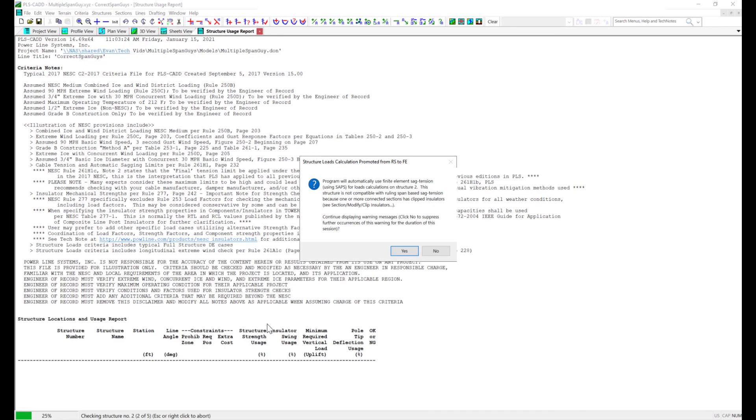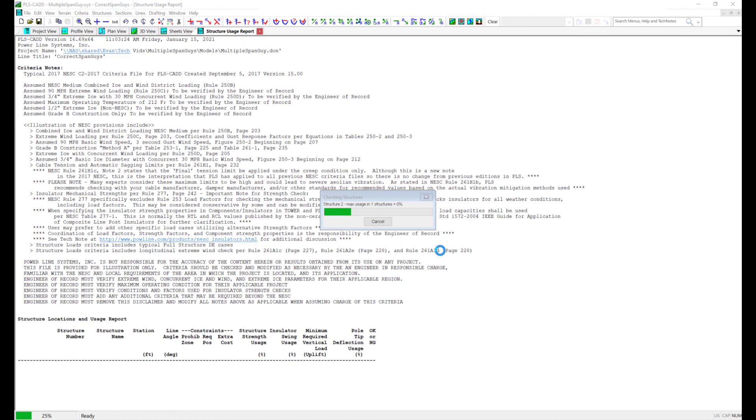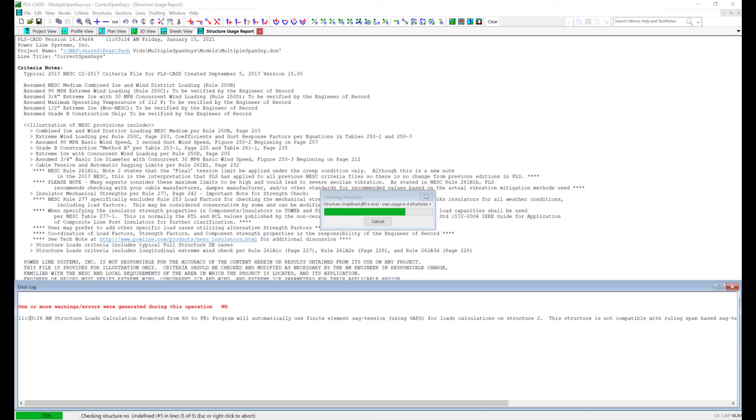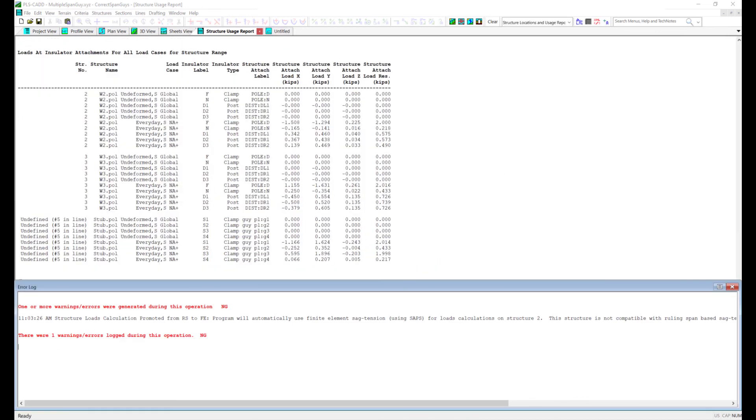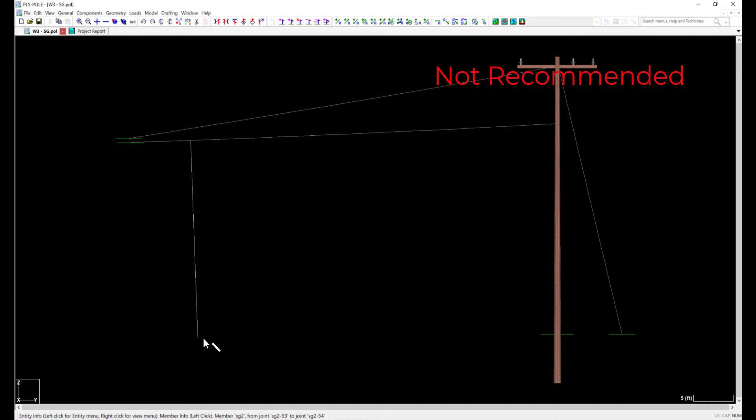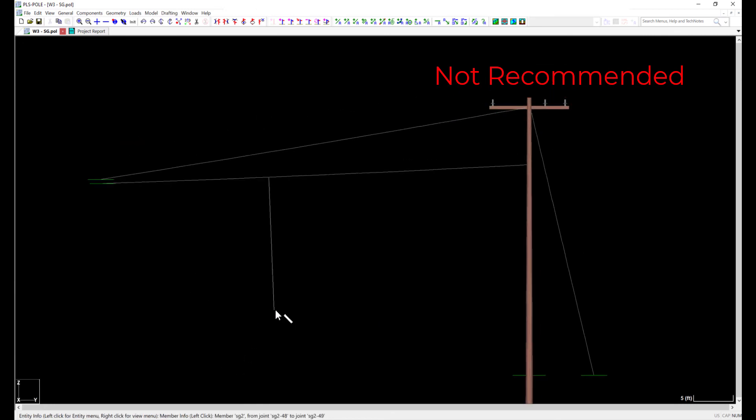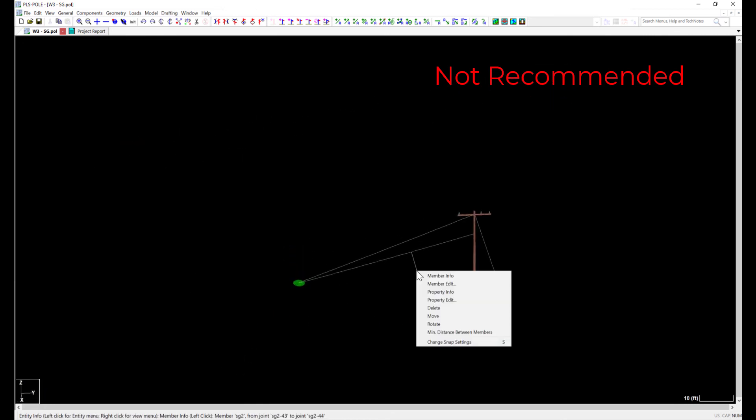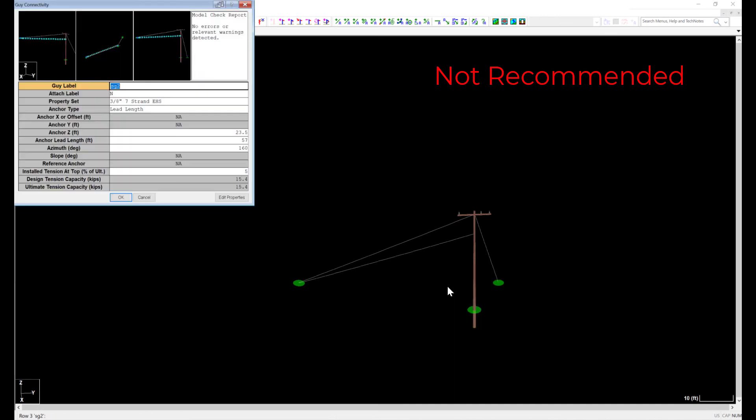I want to point out something while I run this analysis. We see sometimes that users will create separate models, but instead of connecting the models with wire in PLS-CADD as I have done, they will model the span guys with down guys, setting the azimuth, slope, and length to replicate the location of the span guy wire.